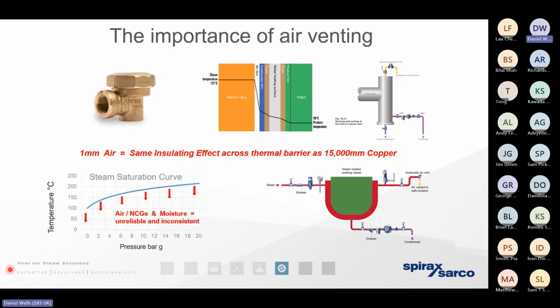Whenever we've got a lot of air in the steam system, for example, when we're starting it up from cold, the steam pressure will move around the infrastructure like a piston, pushing the air ahead of it. So the air will escape across the vent. Then when the capsule sees a higher temperature present within the steam, it will cause that expansion to push down a ball bearing and close the vent. So we look at an air vent at every heat exchanger on the opposite side of the steam inlet. By doing so, it means we can warm the heat exchanger up very, very quickly.